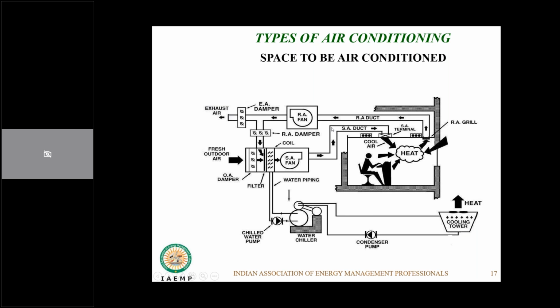Normally, in certain scenarios, when you have a very favorable ambient condition, like in a place like Ooty or Manali and all that, apart from 3 months, your ambient conditions are very favorable. But if you have an enclosed space, you still need some circulation. So you can have the system working in a 100% fresh air mode, where you just bring in the fresh air, you filter it. You may not need your air conditioning system because it is normally quite decent enough, around 20 degrees centigrade, and then you circulate this, and exhaust air is put back out. Or you can control your amount of ventilation rate. You may have 30% air coming in and 70% evacuated out, depending upon your strategy, not adding too much load on your system.